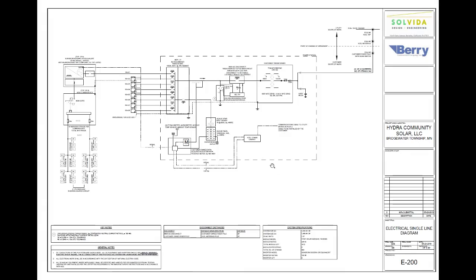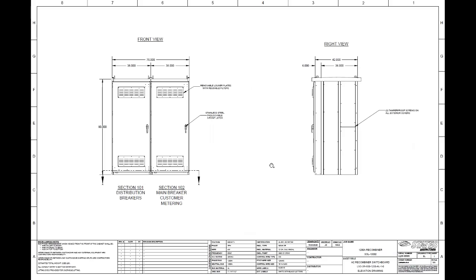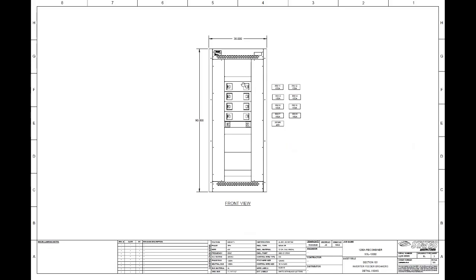And what that ends up doing then is oftentimes it'll just be a 2-section instead of a 3-section switchboard lineup. So you'll still end up with group mounted circuit breakers. You might have a miniature breaker feeding over to a station control power transformer that might be a 3R type transformer that the contractor is either installing on a pad, or we've certainly seen them hanging on the side of the switchboards out in the field.